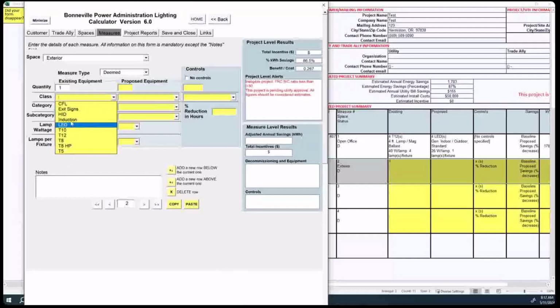So this is where knowing your legacy lighting is helpful. If you don't know what a HID is, that's a high intensity discharge light fixture. It's going to include high pressure sodium, metal halide, or mercury vapor. High pressure sodium is going to be that kind of orangish yellow looking light that you see on a lot of exterior fixtures, especially the schools and stuff like that have some of the old lighting on it. Metal halide is going to be more of a white light, and mercury vapor is too, but mercury vapor as it ages really color shifts to almost kind of a blue light.